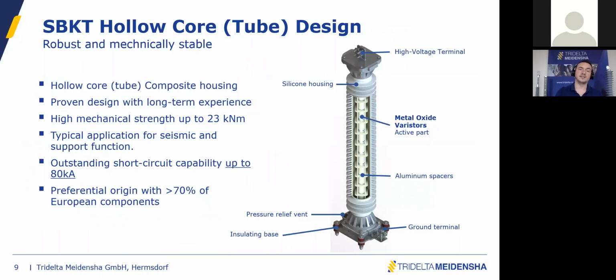Then the second design in the polymer family is the hollow core, also called tube design. You're going to see this design very often for extra high voltage, for 500 kV or 800 kV application, also when specific mechanical strength is required, quite often for seismic application and support function. It's also possible to combine two functions, surge arrester and post insulator, if properly considered during the design stage of the substation. Also outstanding capabilities for short circuit.